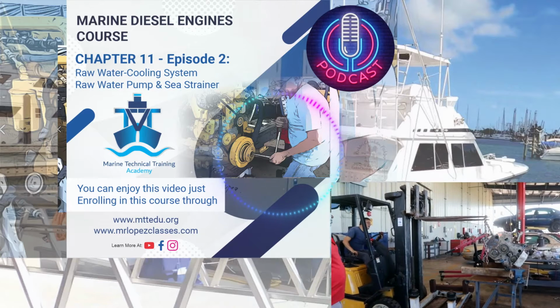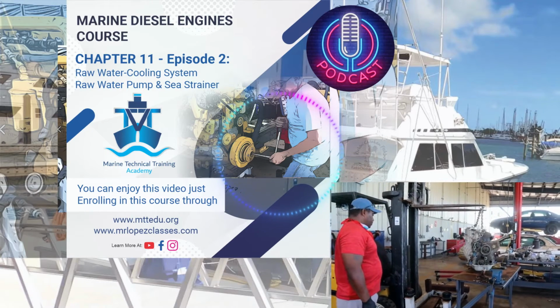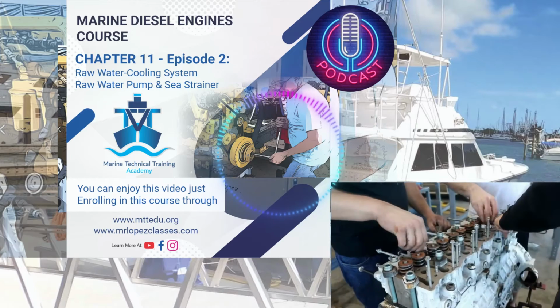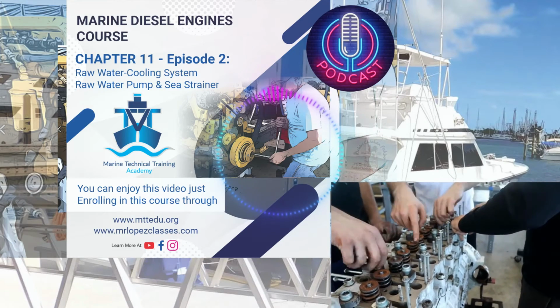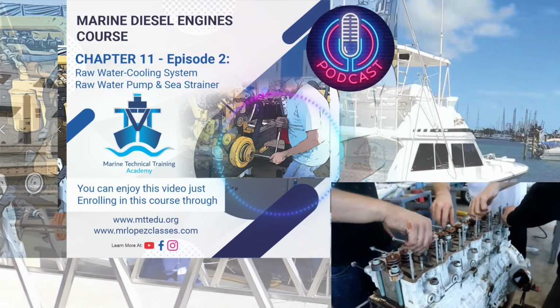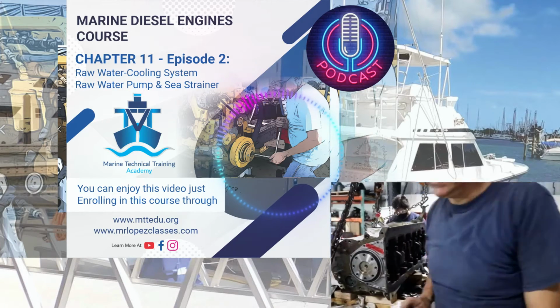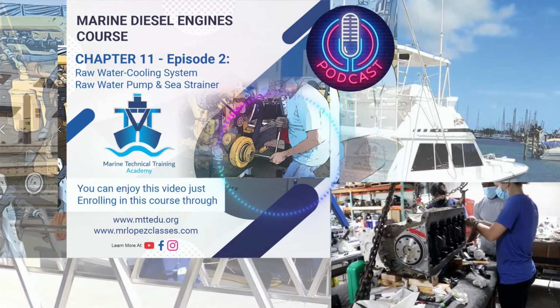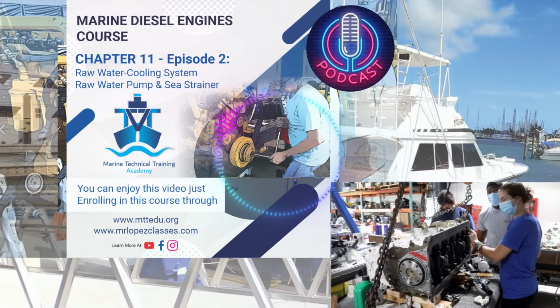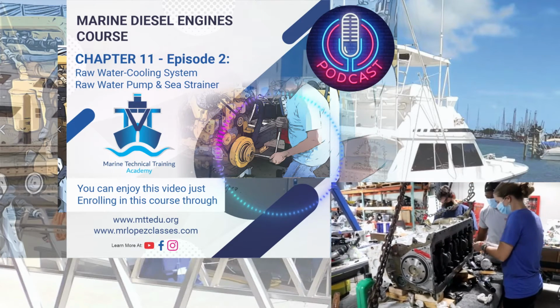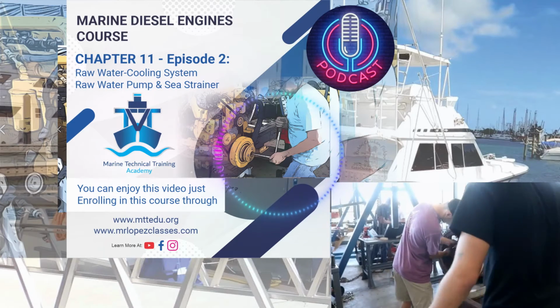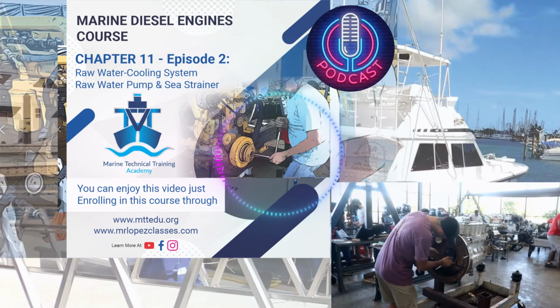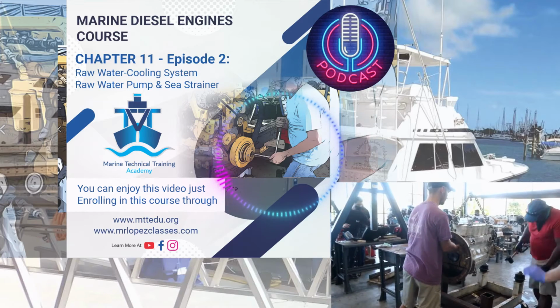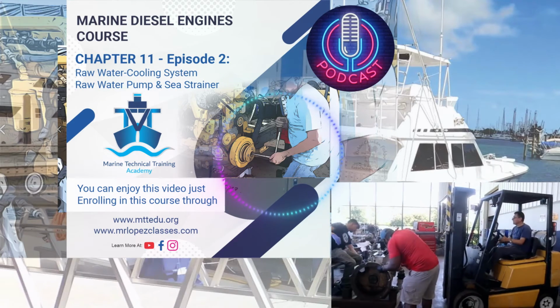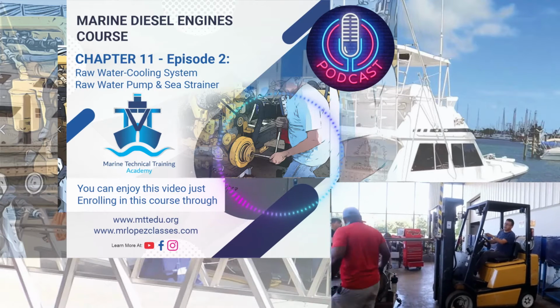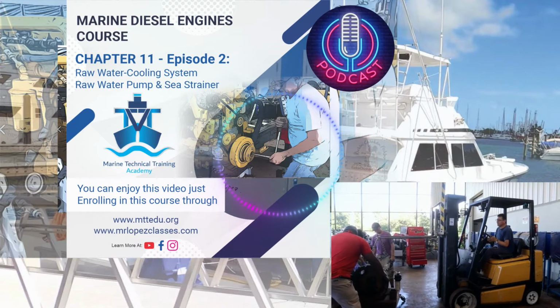Normally, the raw water pump is connected with the belt, and is connected with the crankshaft of the engine, with the pulley of the crankshaft. Immediately, you have access to the pump. The first step is check if the pulley is in good condition. If the pulley has no crack, no dent. And the next step is verify if the pulley doesn't have play. If the pulley has play, it is because the shaft is broken.